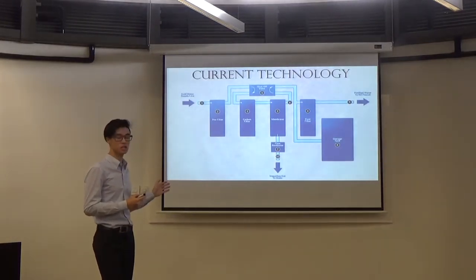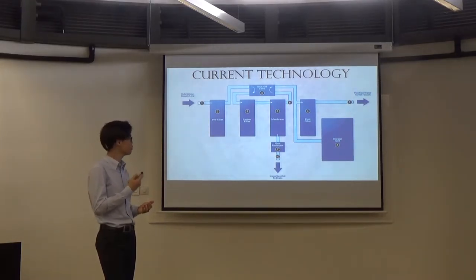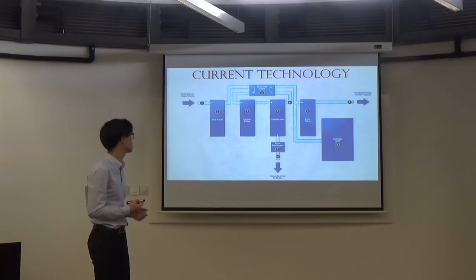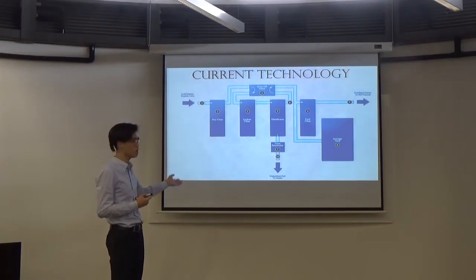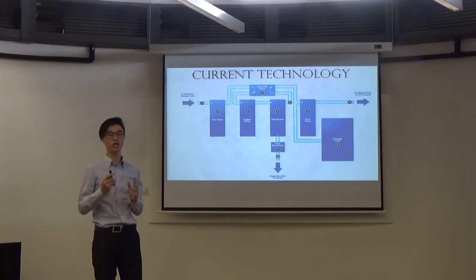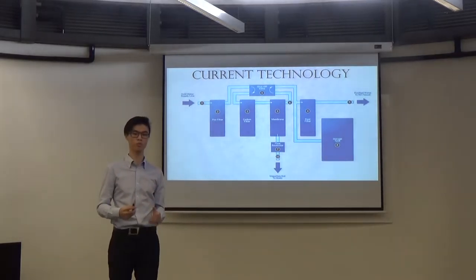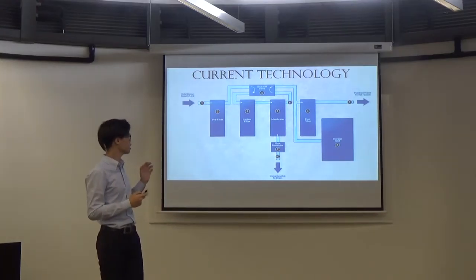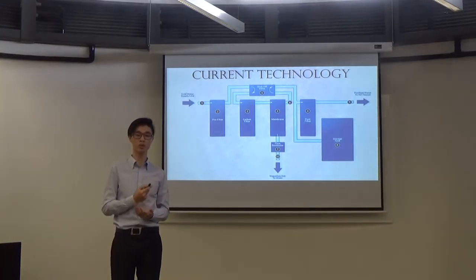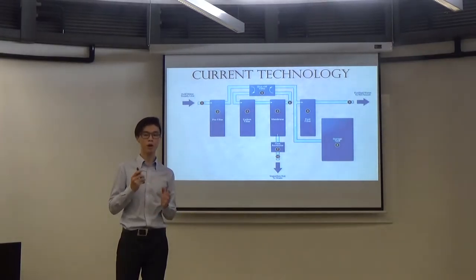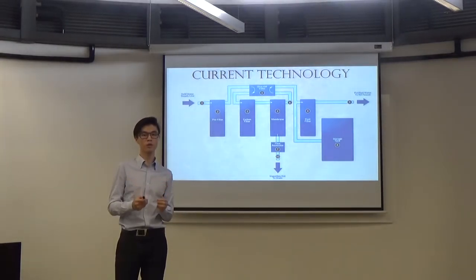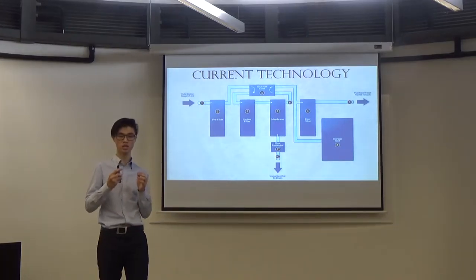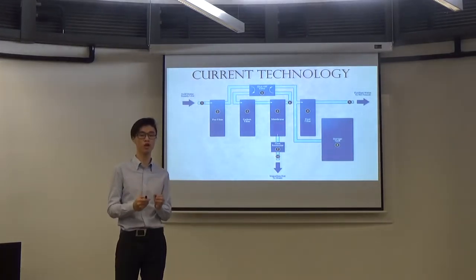This is a typical diagram for the process of reverse osmosis. Pre-filtration is required in two steps: firstly in a pre-filter, and next in a carbon filter, before the feed actually enters the membrane, which would be the main focus for our presentation today. Current technology requires pre-filtration as it removes macromolecules from the feed before entering the membrane, which reduces the fouling rate of the membrane.